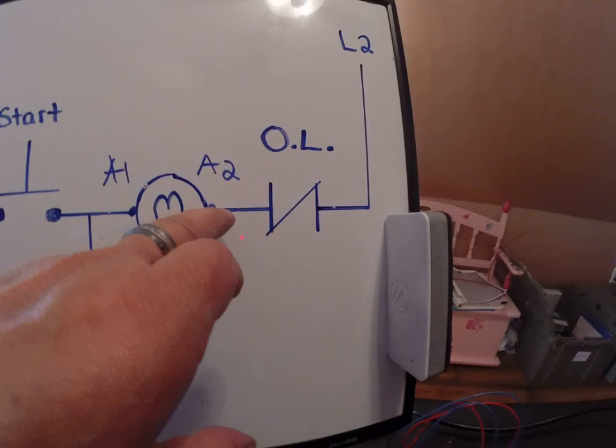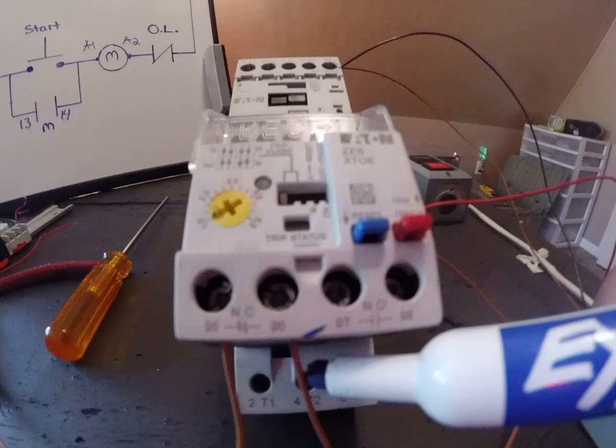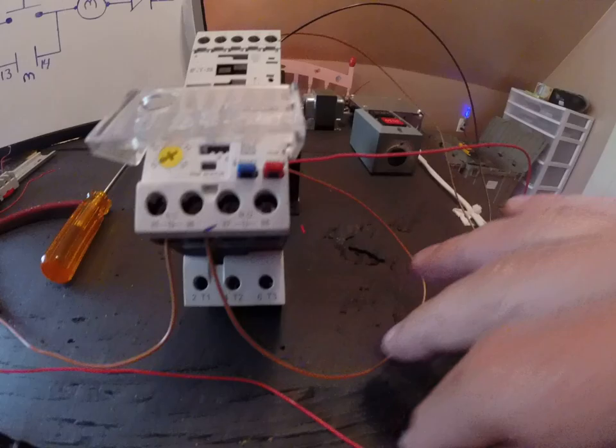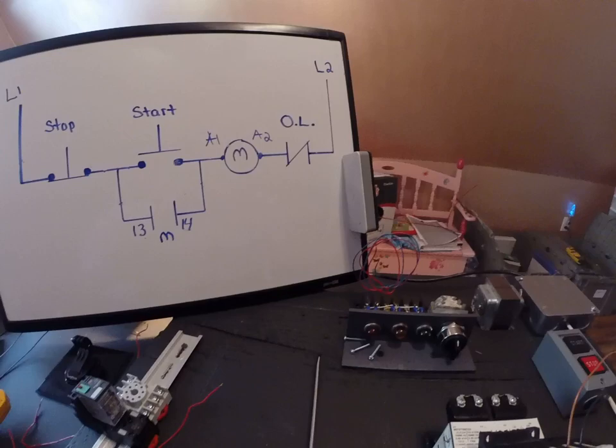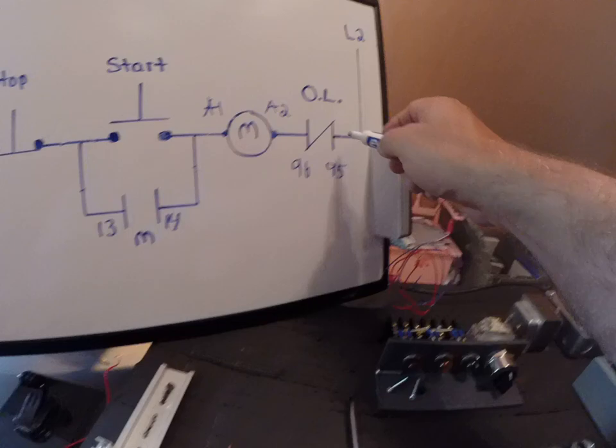So what I'm actually doing is I'm coming off the A2 side of the coil and I'm going into the overload, and I'm actually coming into number 96. If you look right here, I got a wire that comes all the way around and it's brown, and it sneaks into A2. You can kind of see it coming into A2, difficult to get the wire under there. So I'm actually leaving A2 and going into 96, and I'm leaving number 95 - you can reverse it if you want, it'll still work. I'm leaving number 95 and going back to my 24 volt source because that's what this coil is. So I leave number 95 and go back home to my source voltage.